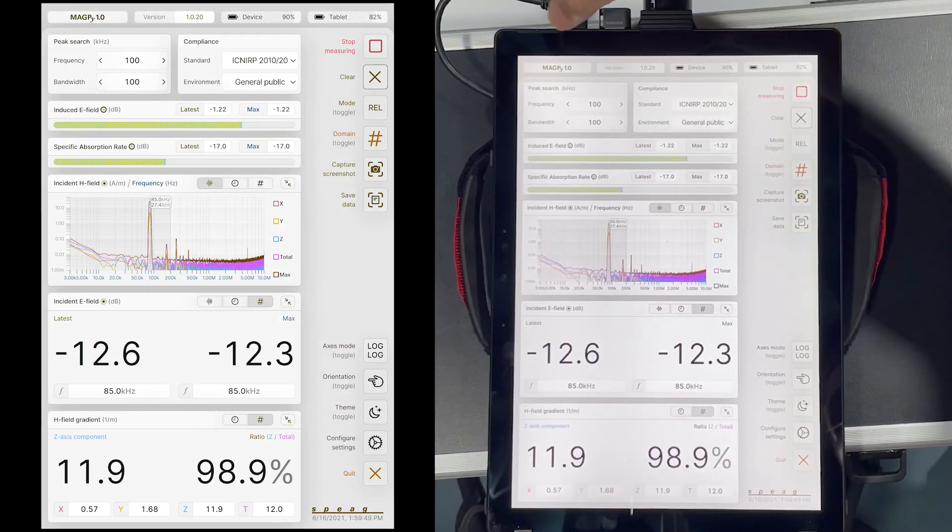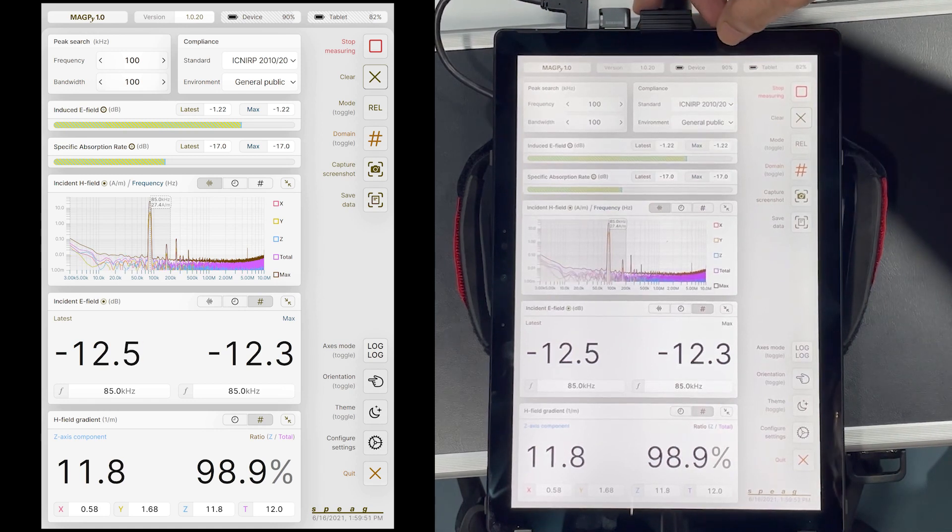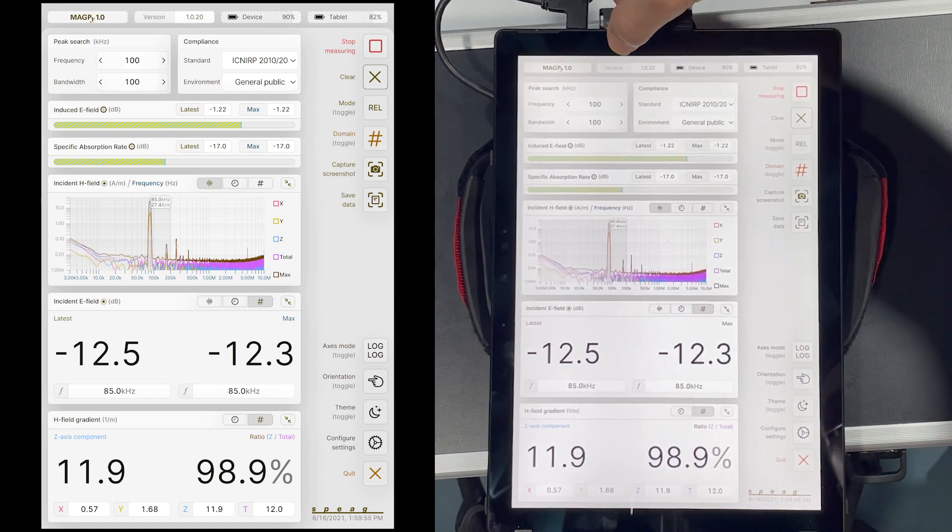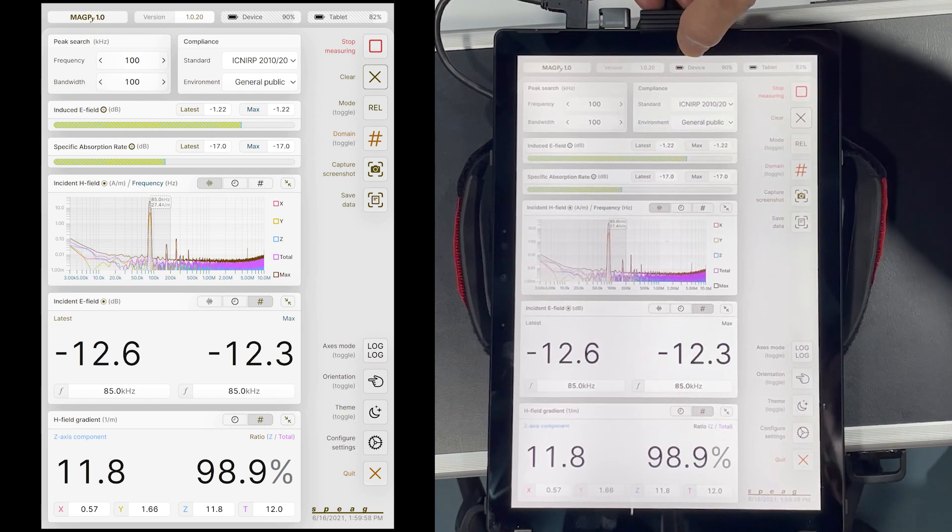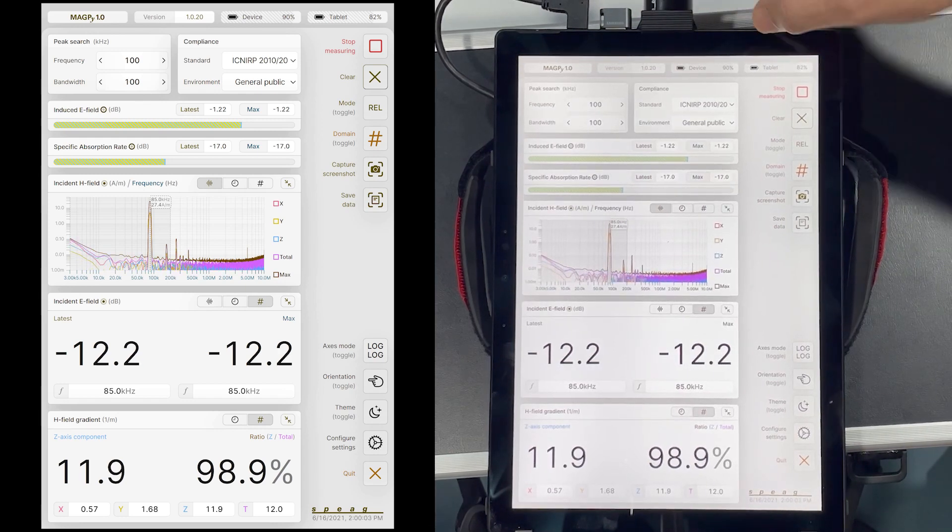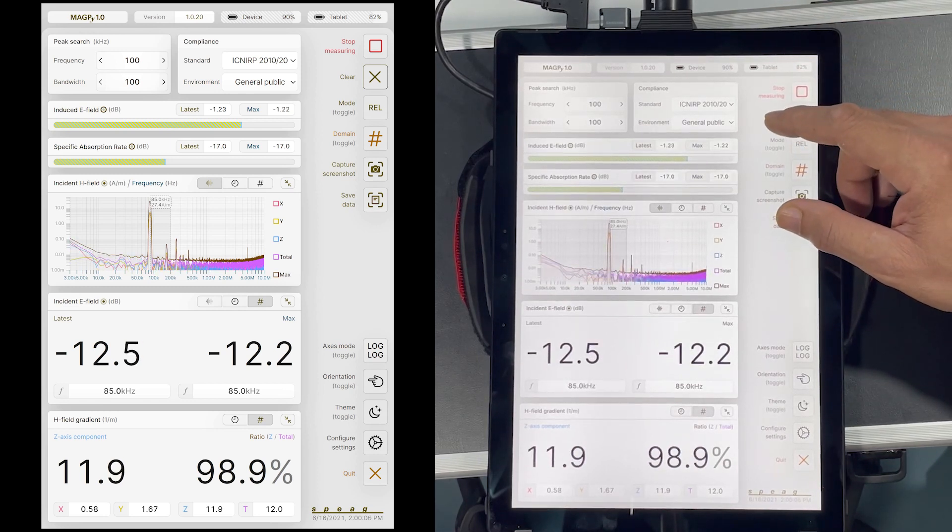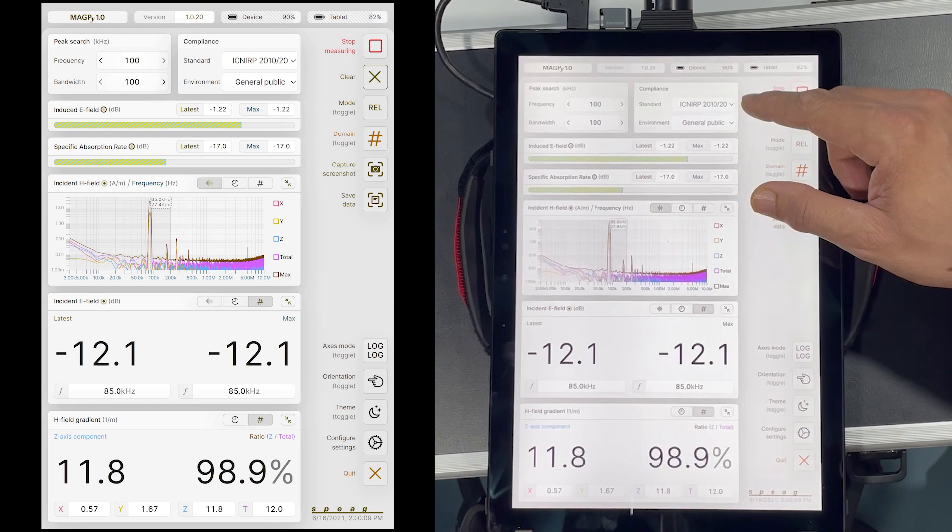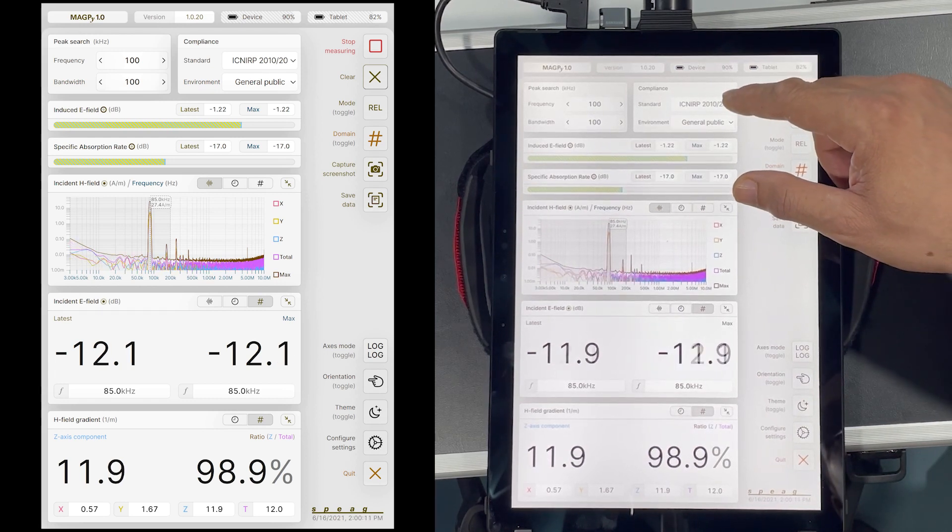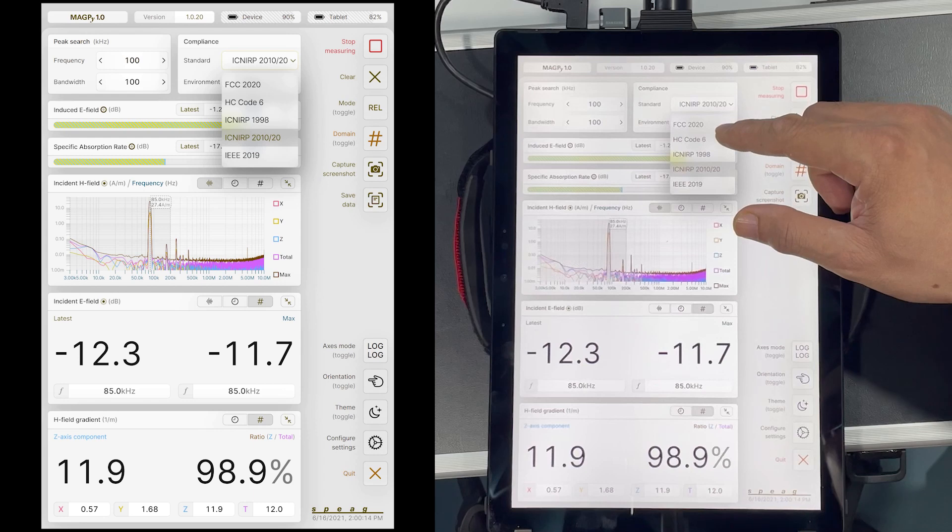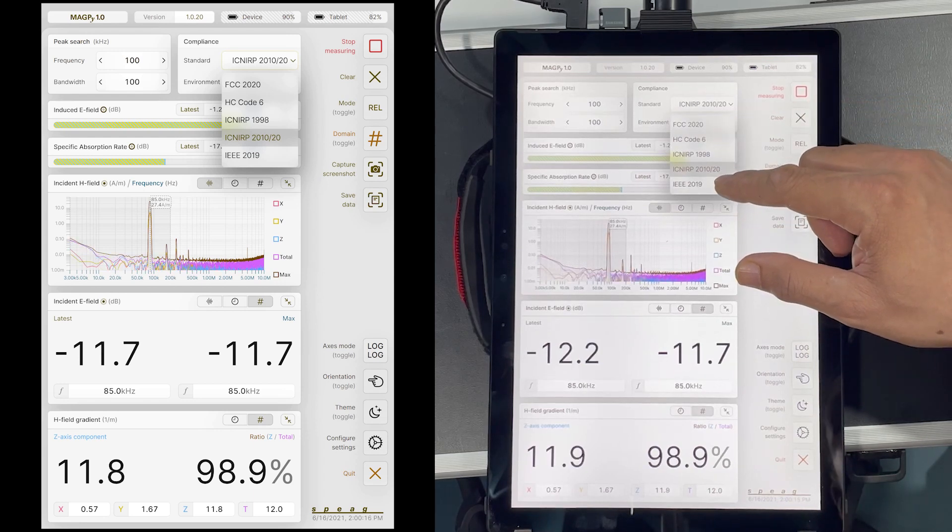The top of the user interface window shows the current software version, the battery status for the Magpie DAS as well as the tablet. Magpie already has several standard limits pre-programmed for comparison with measured values. Let us see. So, we have ICNIRP, we have FCC, HC Code 6 and IEEE limits.